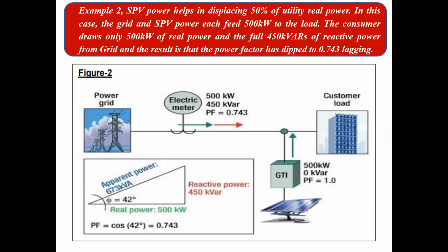Now let us see that the customer has installed a solar PV system, and it is generating 500 kilowatt, while the remaining 500 kilowatt is fulfilled by the utility grid through which it is connected. But the kVAR it draws would be the same, 450 kVAR. Because of this, the real power is changing: in the previous scenario the real power was 1000 kilowatt, whereas now it is 500 kilowatt. So the power factor changes, and it has changed to 0.743. Please move to the next slide.